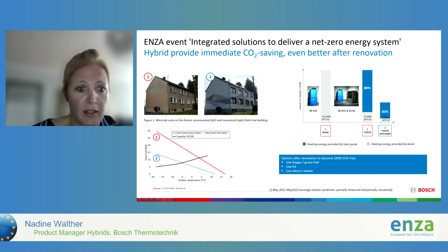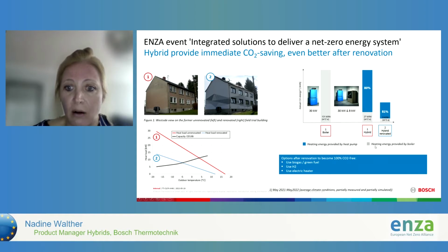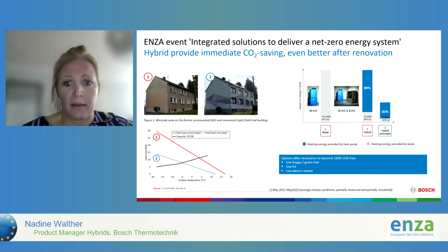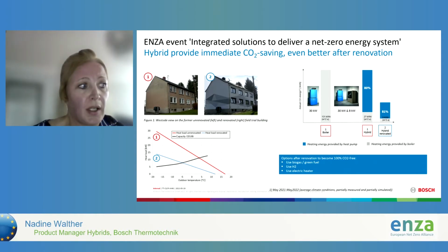And then number 2, the graph in blue, shows the heat load in a renovated building. So you can see that the overall heating energy has significantly been lowered, but we can see that the share of the heat pump is not rising dramatically anymore. And the total heat load is being reduced, and the heat pump is covering the biggest share of it. So after renovation, as we can see here, only 14 kilowatt are needed instead of the 30 kilowatt to warm up the building. So that's a significant reduction, as you can see on the far left down there. So there was a big improvement.